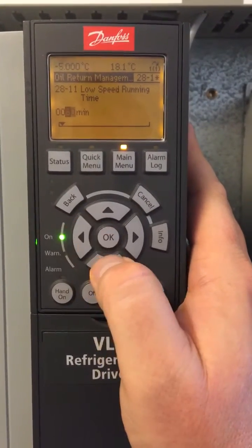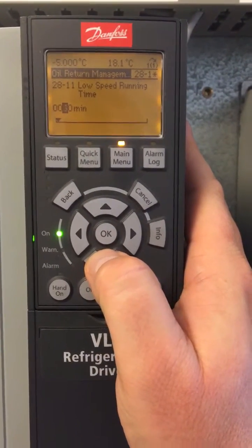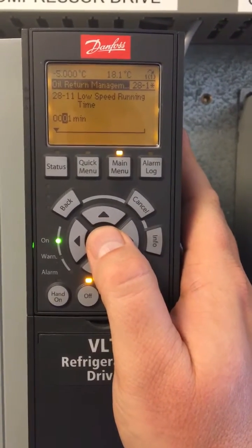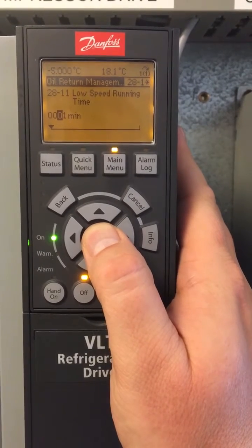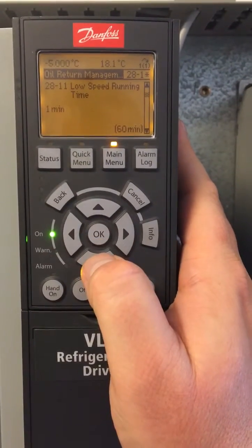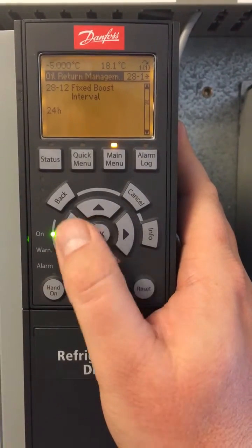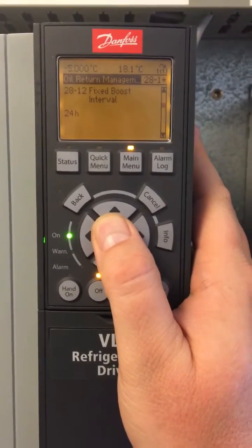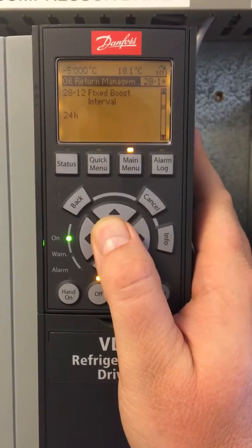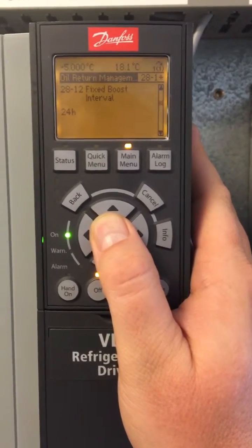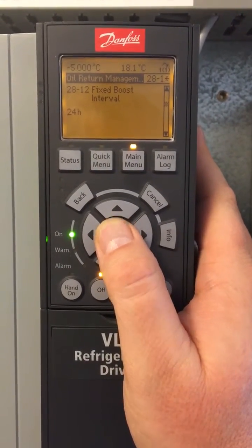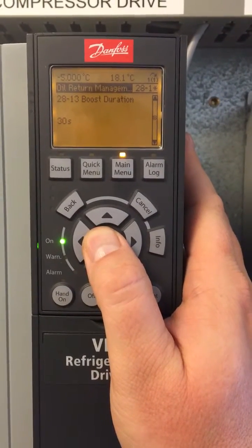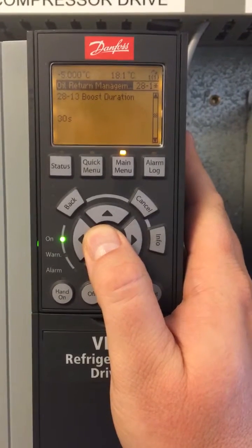I'll program 1 minute for this demonstration purpose. This is usually too short, but in this case it will be okay for demonstration purposes. Click OK to that, and we go to 2812, and you have the possibility to let the drive pick up speed at fixed intervals. This could be every hour, it could be every 2 hours, or 24 hours, or every 2 days.